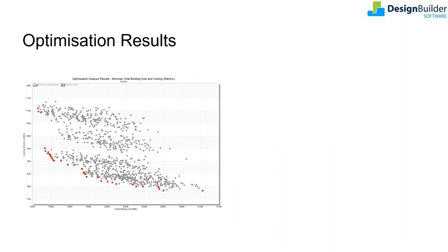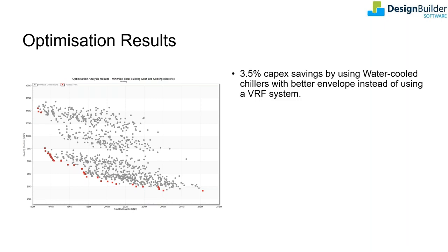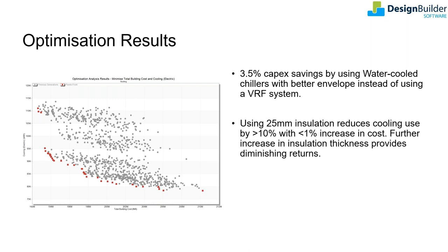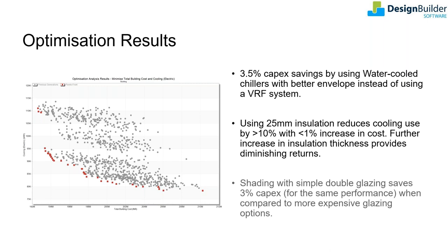Similar clusters and sub-clusters were analyzed and answers to the design questions were sought. Water-cooled chillers were found to be better — with a better envelope, similar performance to VRFs can be achieved with 3.5% capital cost savings. The effect of adding insulation and thermal mass is also seen, however adding insulation beyond optimal levels provides diminishing returns. Also, shading with simple double glazing saves 3% capital cost for the same performance when compared to more expensive glazing solutions. There are obviously more inferences that can be drawn, but the intent here is to show you the process.